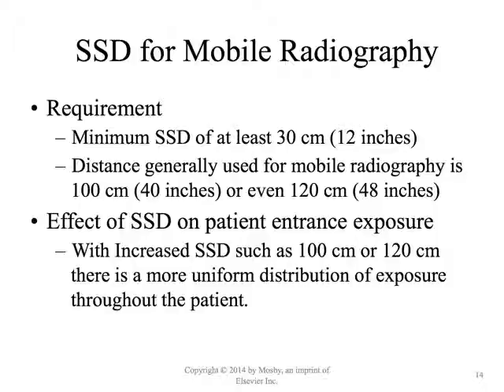This is very, very important to the X-ray techs here, is knowing the SSD. People in radiation therapy talk about SSDs all day long, but it's the source to skin distance, right? And so for us in X-ray, anytime we're messing around with mobile radiography, the minimum would be 12 inches. And I don't think there's any facility that you've ever worked at that's shooting mobile X-rays at 12 inches, right? In general, we're talking about 40 inches, trying to get close to 72 for portable chests.